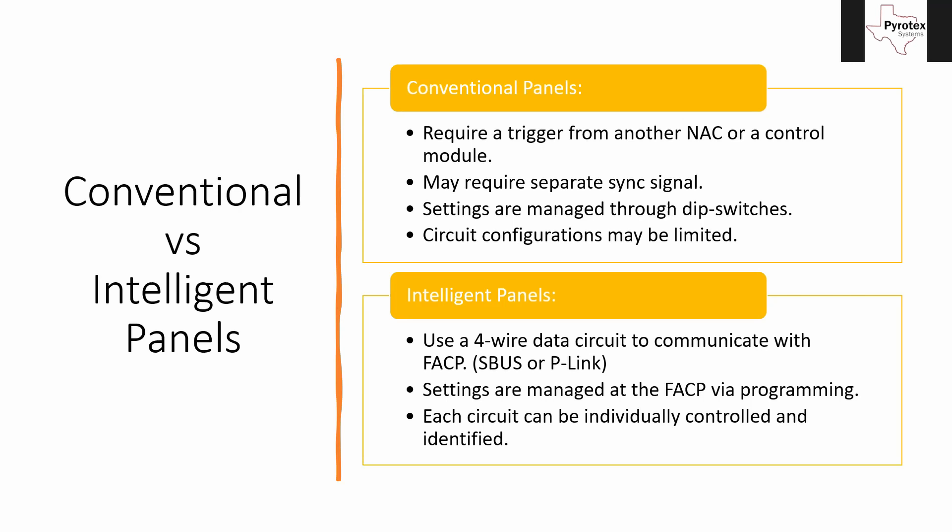The other type of panels we have are intelligent panels. Most of our schools or anything with a Silent Knight or Farenhyt panel gets these intelligent ones. They use a four-wire data circuit to communicate with the control panel, so they don't have a separate sync signal. Any signal communicating between the two is going to be over that four-wire circuit. In the case of Silent Knight or Fahrenheit, that's called SBUS.